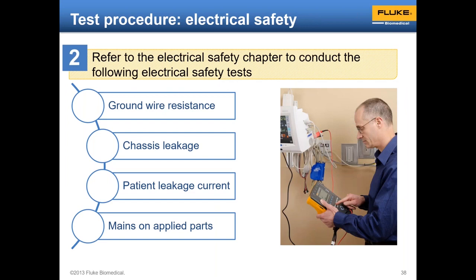And finally, we come to the electrical safety part of the testing. We will measure the ground wire resistance and the leakage current to ground. We will measure what is called chassis leakage in the 62353 and the IEC 60601-1 3rd edition. Chassis leakage is now called touch current. And the reason it's called that is because it is the current that could flow to the patient if the patient were to touch the medical device, or if the nurse or the doctor were to touch the medical device and be touching the patient at the same time. That's called touch current for good reasons.